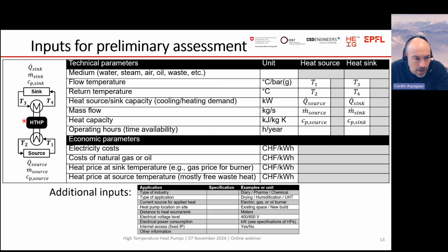Then if a heat pump is a possibility, we need information on the temperatures of the heat source and heat sink, the capacities, then also the flow rates and the medium. Is it water, steam, air, and so on? Operating hours. We need some economic parameters like the costs for the electricity to run the compressor, the costs for the other energy carrier that is used today, for example gas or oil, and maybe also some additional cost for the source. Maybe it's a district heating network, that would also be costly as a heat source, or if it's waste heat, it's almost free. So these are questions that need to be clarified at the very beginning.